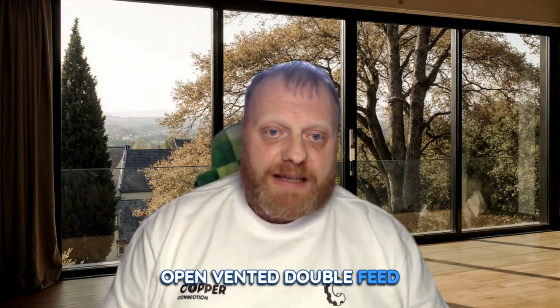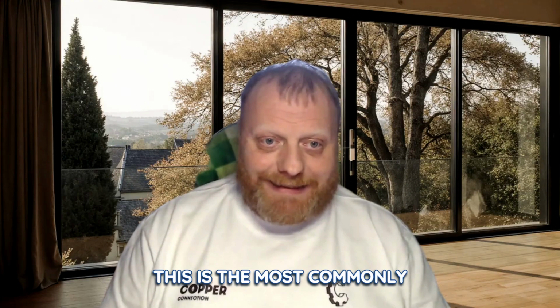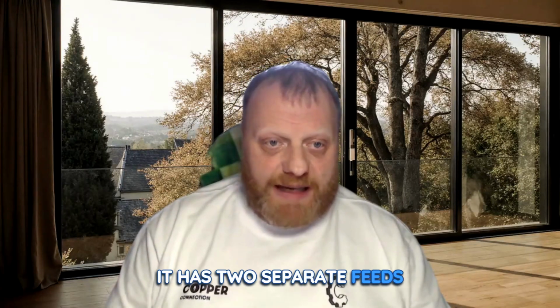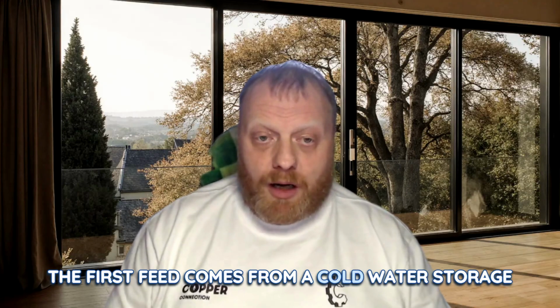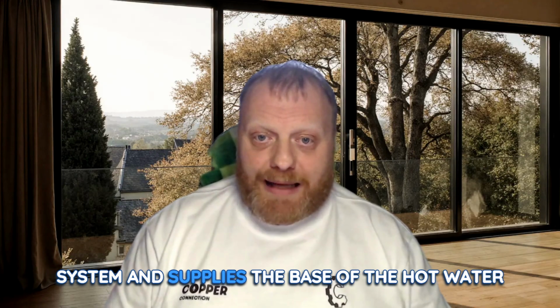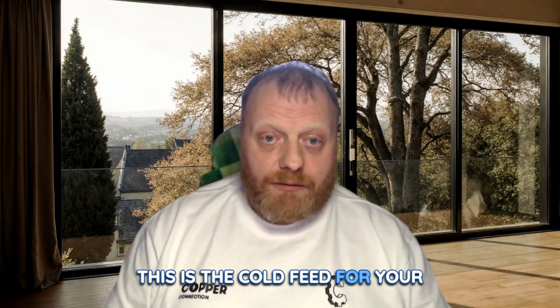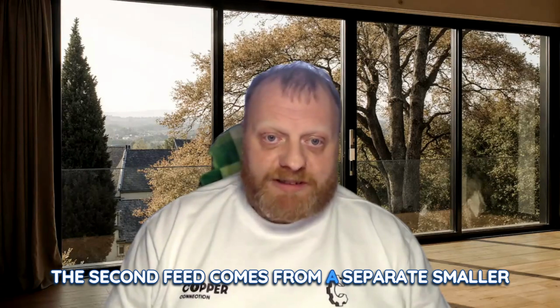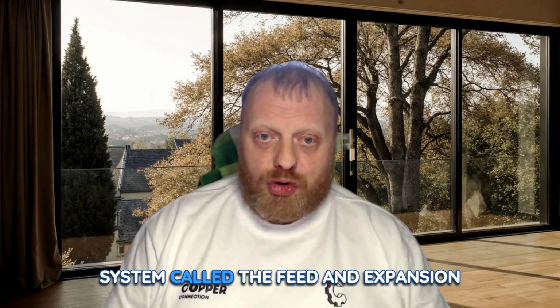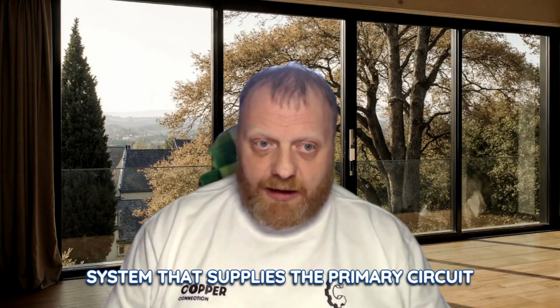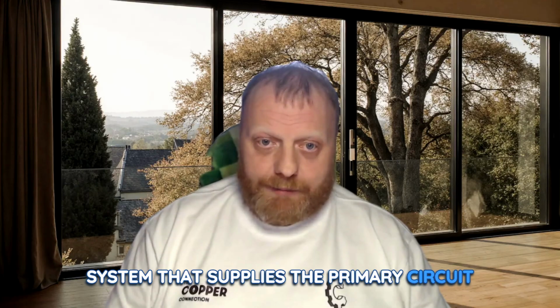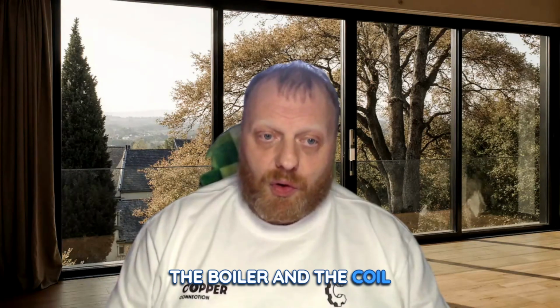Open vented double feed indirect system. This is the most common traditional indirect system. It has two separate feeds. The first feed comes from a cold water storage system and supplies the base of the hot water cylinder. This is the cold feed for your domestic hot water. The second feed comes from a separate, smaller system called the feed and expansion system. This supplies the primary circuit, the boiler and the coil.